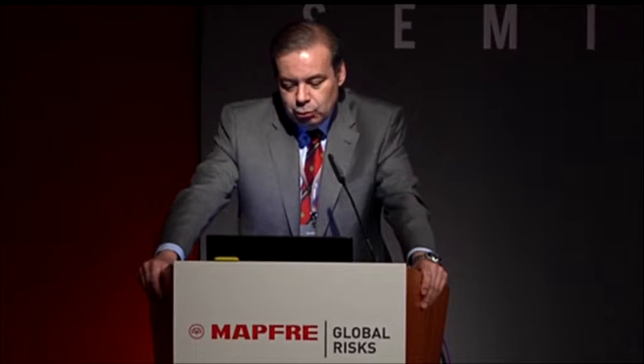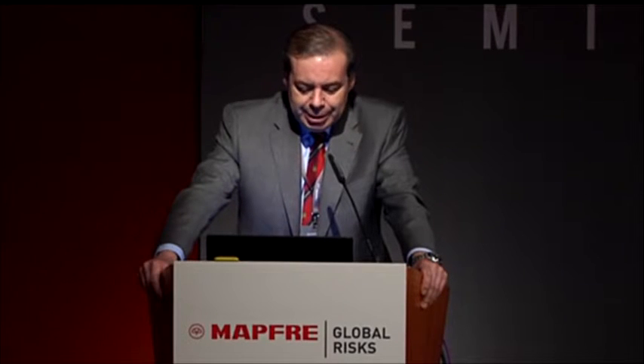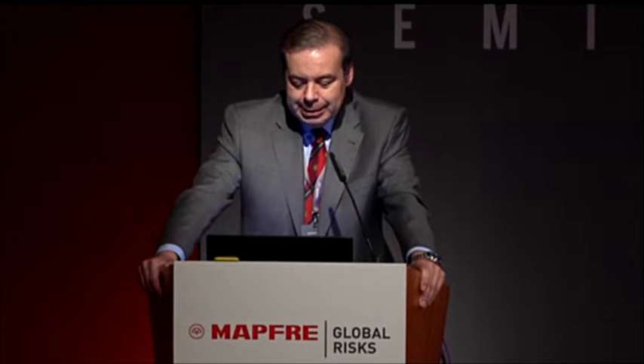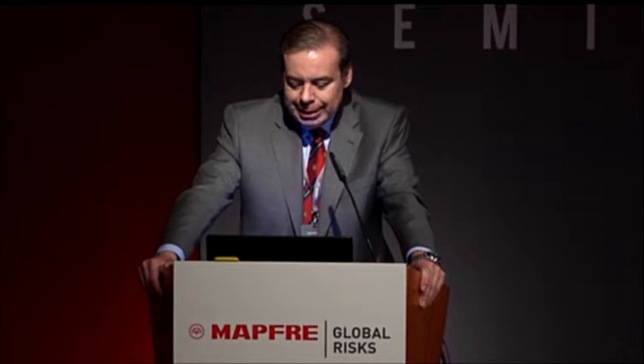If we try to understand each of these phenomena, we see that low cycle fatigue can be defined as the gradual damage or degradation of a material produced as a result of subsequent heating and cooling cycles that translate into expansion and contraction of the material. There is a plastic deformation, and this thermal fatigue occurs mostly during startups, outages, shutdowns, and load variations.